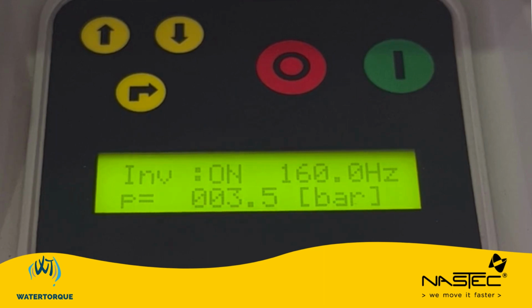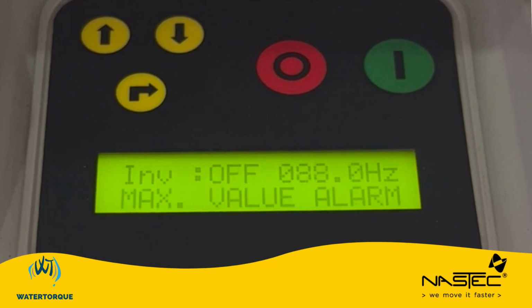Now I will shut off the valve, which is going to have us fault out on max alarm value. And we are set. That's how we set MPPT.